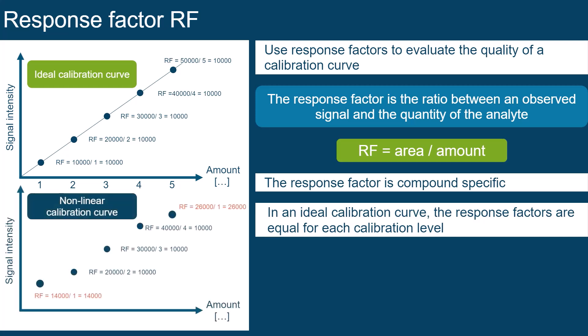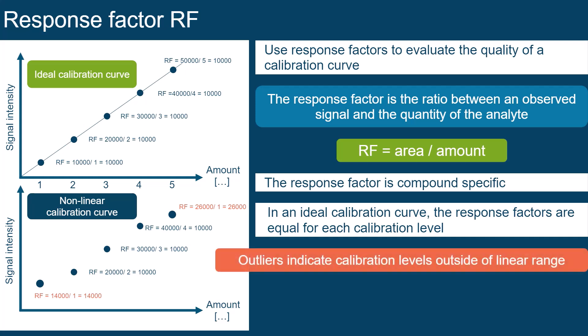In this extreme example of a non-linear calibration curve, the response factors of the lowest and the highest levels have different RFs. This is a mathematical indication that these levels are outside of the linear range. By using the response factors, you do not need to rely on an optical assessment.